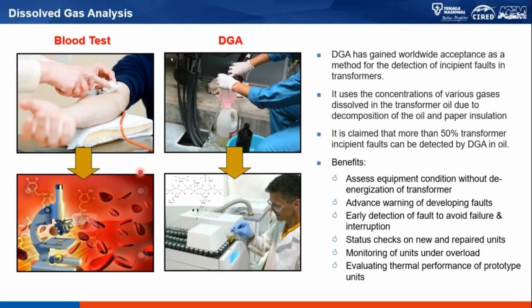So what are the benefits of doing DGA? Let's have a look at one by one. We can assess our transformer without having a shutdown. We can use the DGA as a basis for advanced warning when certain faults are developing. And because we are talking about the incipient fault, that can give us an early detection to avoid failure and interruption. Of course, we can use DGA as our status check after we have repaired or done something on our transformers.